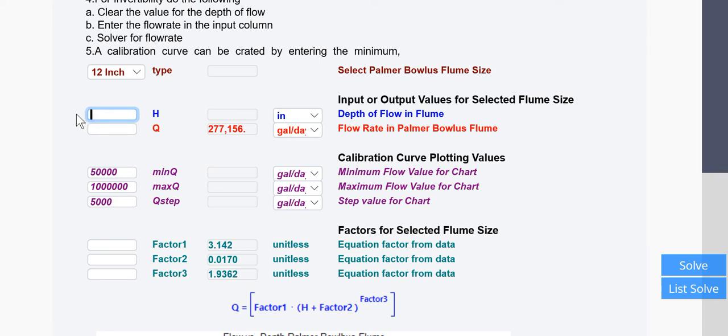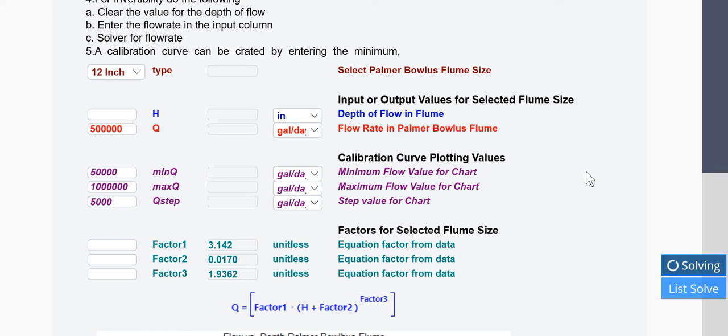If I blank this and put in 500,000 gallons a day, you'll see that now it says I've back-calculated that if my flow meter is reading 500,000 gallons a day, I can calibrate it because I can check and see that there's 5.5 inches in there.